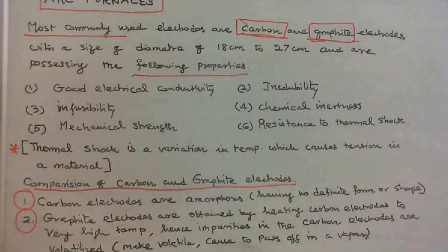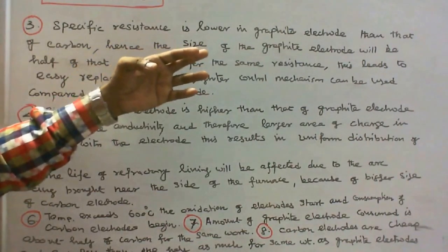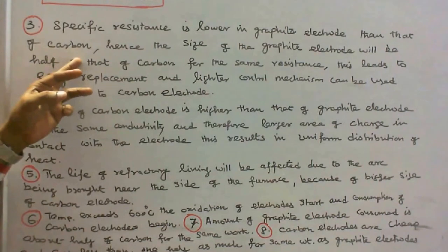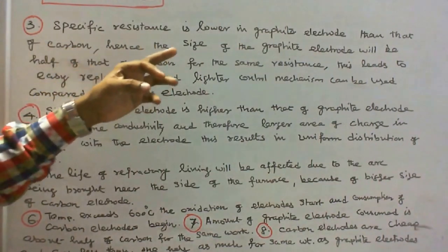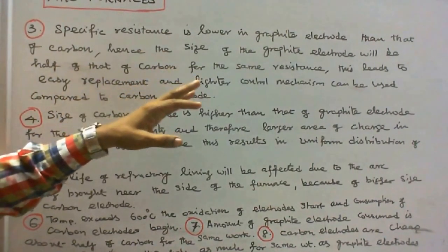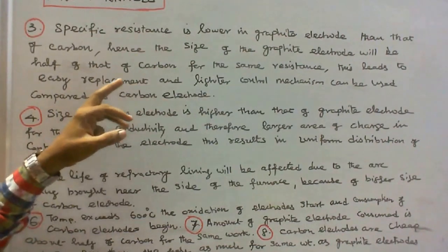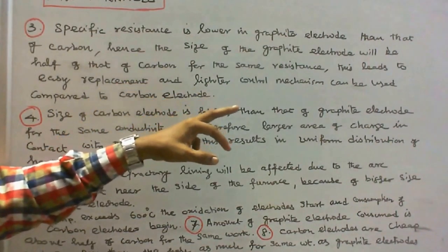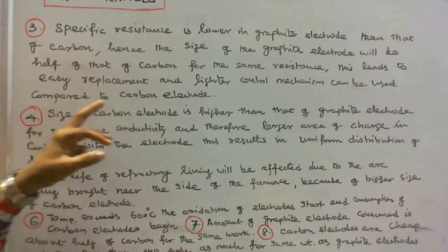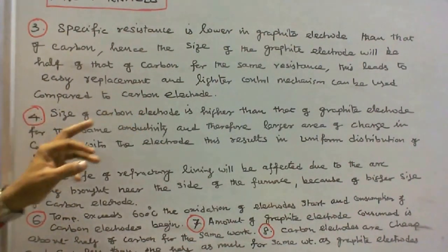Number three: specific resistance is lower in graphite electrode than that of carbon. Hence the size of the graphite electrode will be half of that of carbon for the same resistance. This leads to easy replacement and lighter control mechanism can be used compared to carbon electrodes.